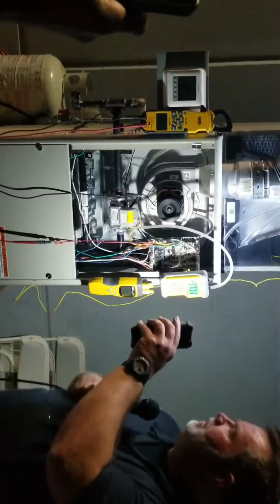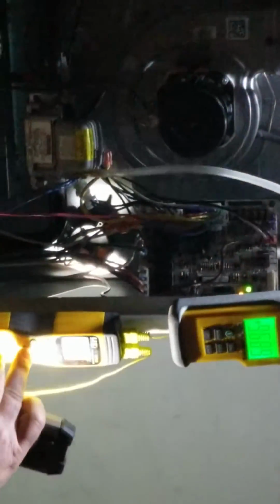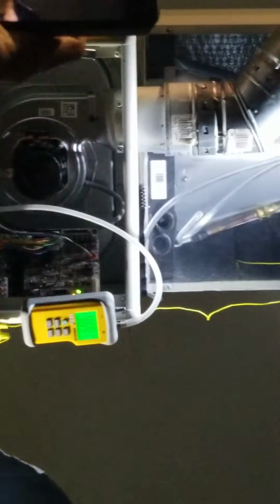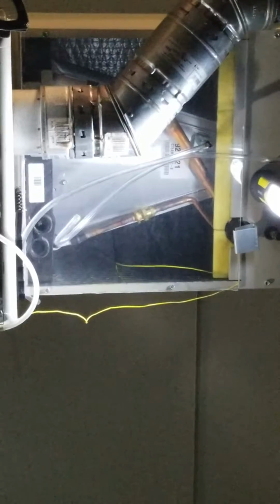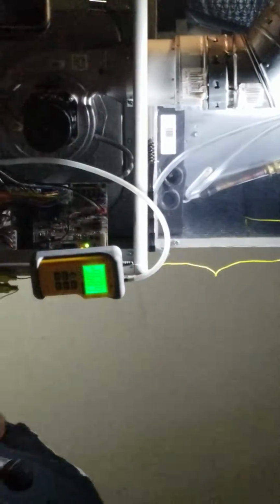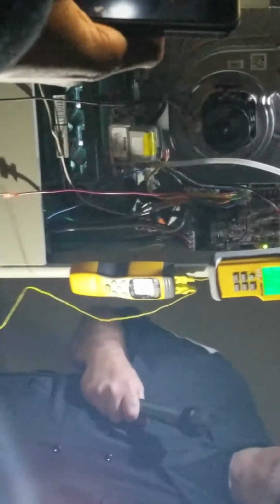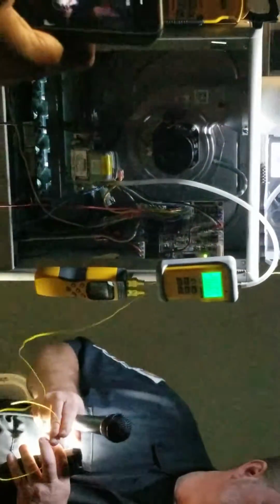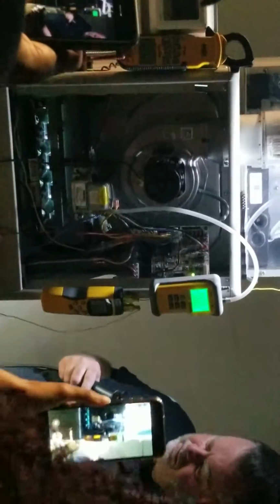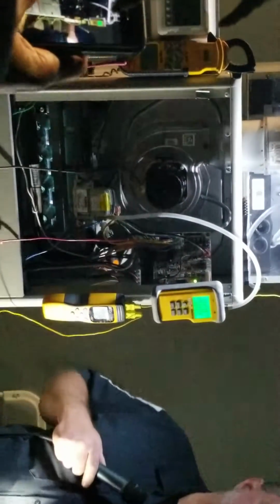The board does a couple of things, but what I'm going to do here is first take a temperature going across my heat exchanger so you guys can see the readings. You see my temperature rise across my heat exchanger? Where are they wired? Just a little thermocouple. It's just sticking up in there, and I just got it stuck in the return. Simple. Does that make sense, guys? See what it looks like on the outside? Huh? It's right there. Is it like a sensor? It's just a thermocouple wire. There's the K-type thermocouple. Read it. Make sense? Easy.